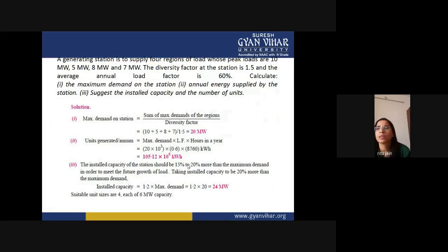So you can see that the loads which are given are 10 megawatt, 5 megawatt, 8 megawatt, and 7 megawatt. Diversity factor is given. The formula for diversity factor is equal to the sum of individual maximum demands divided by the maximum demand of the station. So you can easily calculate the maximum demand on the station by using this diversity factor. The peak loads of individual regions are given: 10 plus 5 plus 8 plus 7, divided by 1.5. So you can easily get that the maximum demand on the station is 20 megawatt, right?